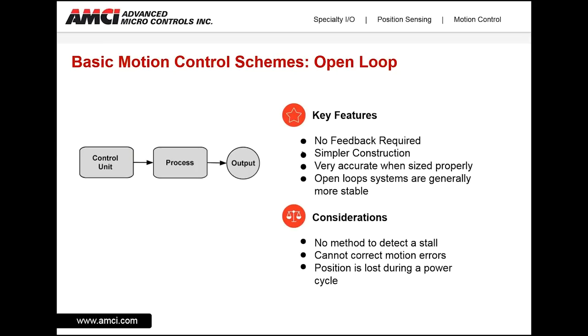Open loop systems can be very accurate when sized properly, and are generally more stable. Some of the considerations are: there is no method to detect stall, so if the motor stops, we will be unaware of that. We cannot correct for motion errors, and if the position is lost during a power cycle, there is no way to re-establish position on power-up.